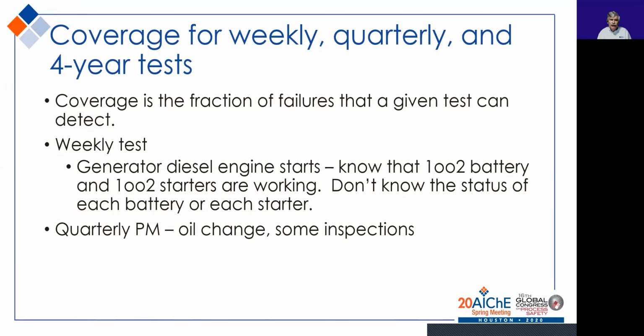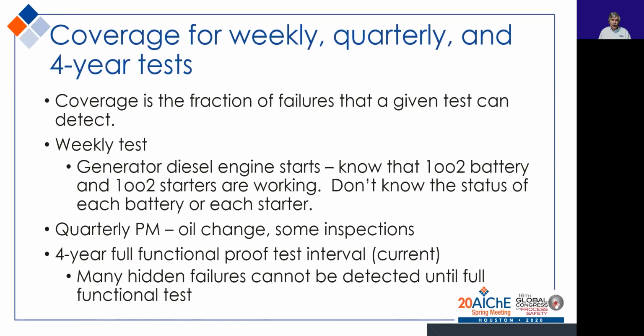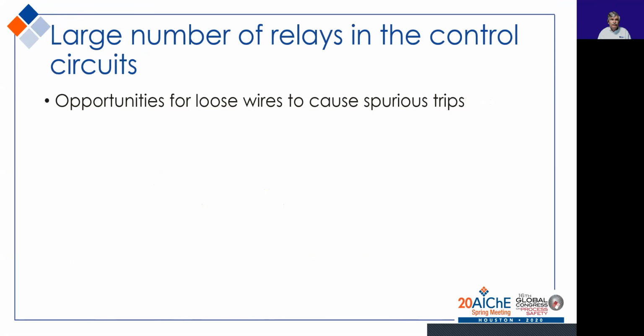For the quarterly PM with an oil change and some inspections, we are not able to detect very many hidden failures. In the 4-year full functional test, now we can detect many hidden failures, but it's 4 years before we can do it because none of the other tests have the coverage to find them. We have a large number of relays in the control circuits where there are opportunities for loose wires to cause spurious trips.